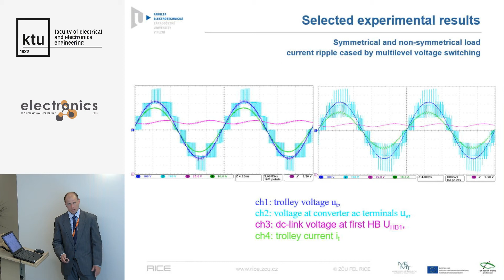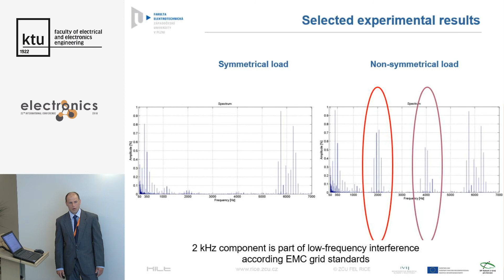In the harmonic analysis for the symmetrical load, the main parts are around 6 kilohertz. However, during non-symmetrical load, there are components at 2 kilohertz and 4 kilohertz, and the problematic one can be the 2 kilohertz component, because it's a part which is necessary to compute for the THD according to EMC grid standards.